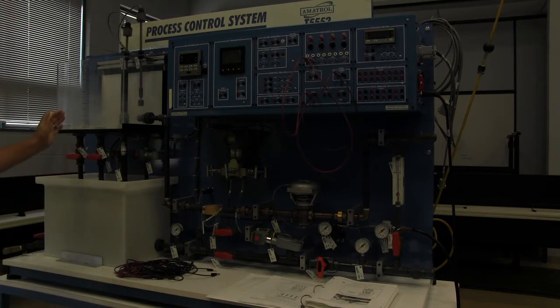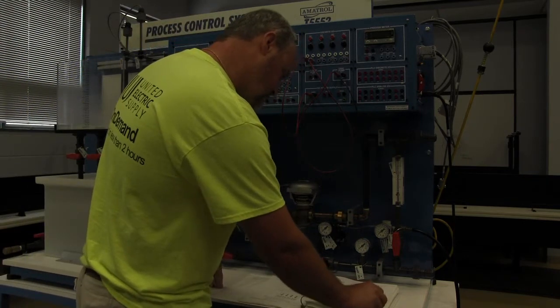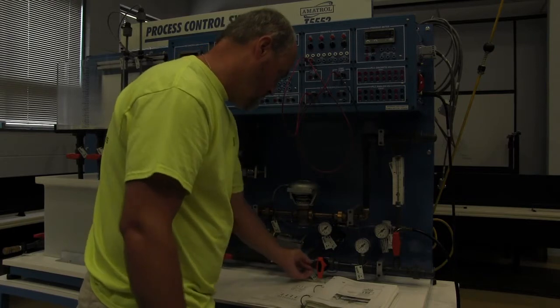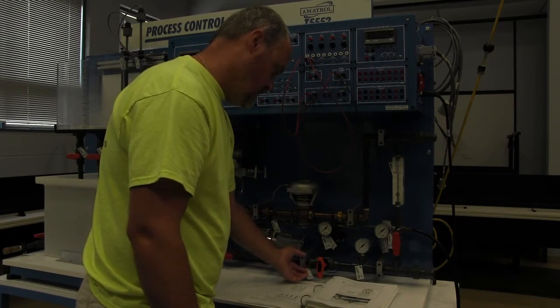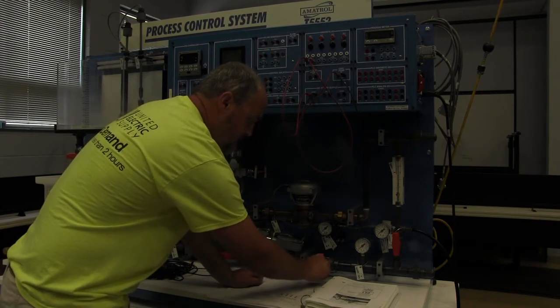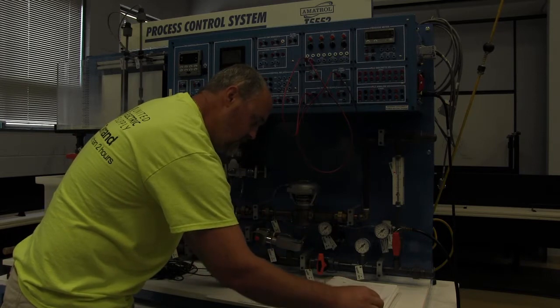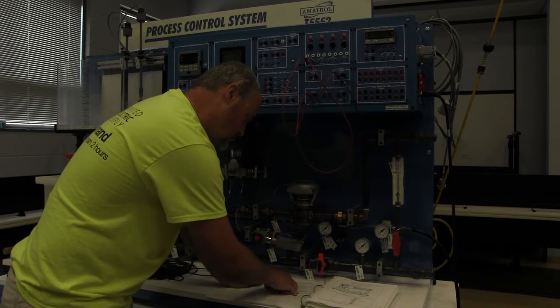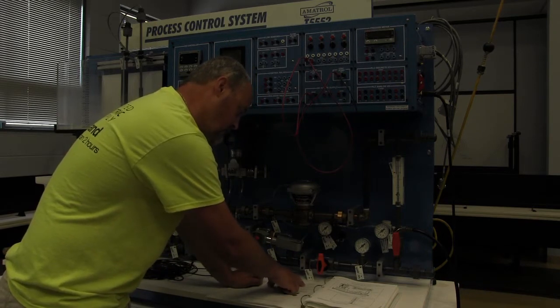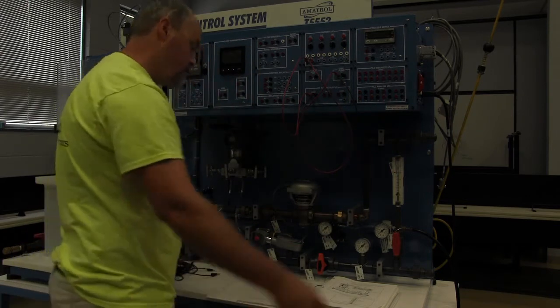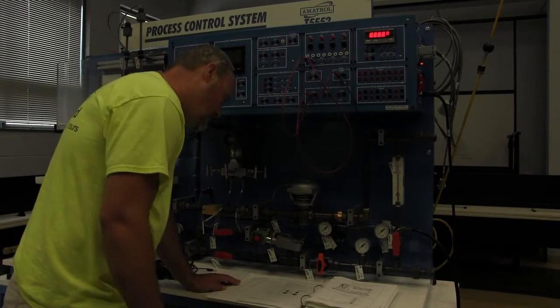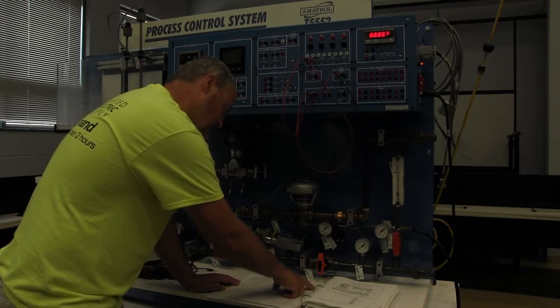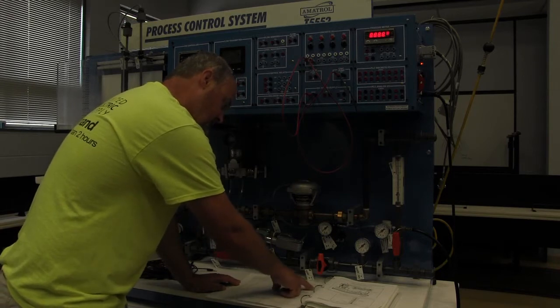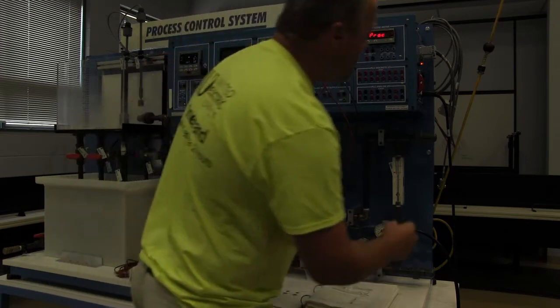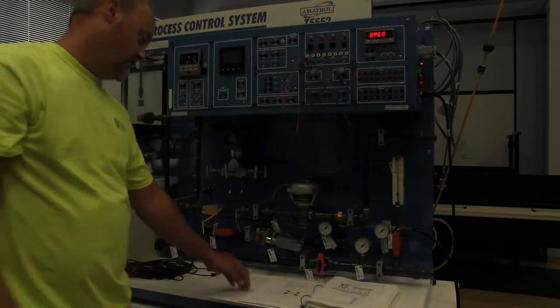So as you can see, these are now sideways rather than in line with the pipe, so they are closed. Make sure the manual flow valve FV100 is completely closed, fully clockwise. So that's the clockwise position. Make sure the T5552 electrical power cord is connected to the outlet, which it is. Turn the main breaker on. The control power indicator light above the circuit breaker should be lit, indicating the control power is present. If the indicator light is not lit, check the power cord to make sure that it's plugged in. We are lit, and we do have some devices lighting up so we know we're lit.